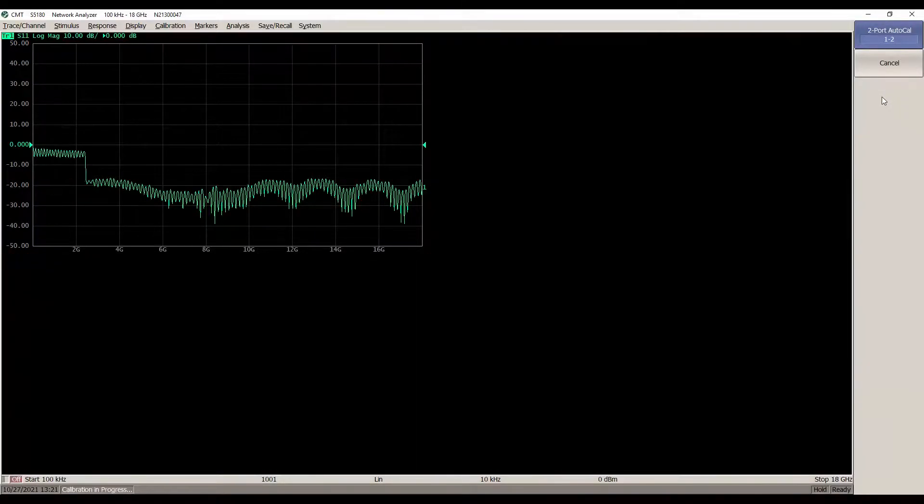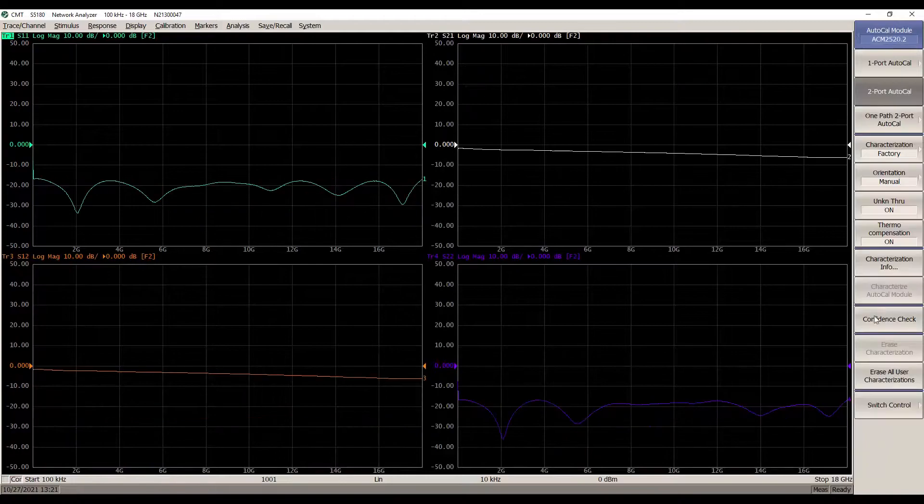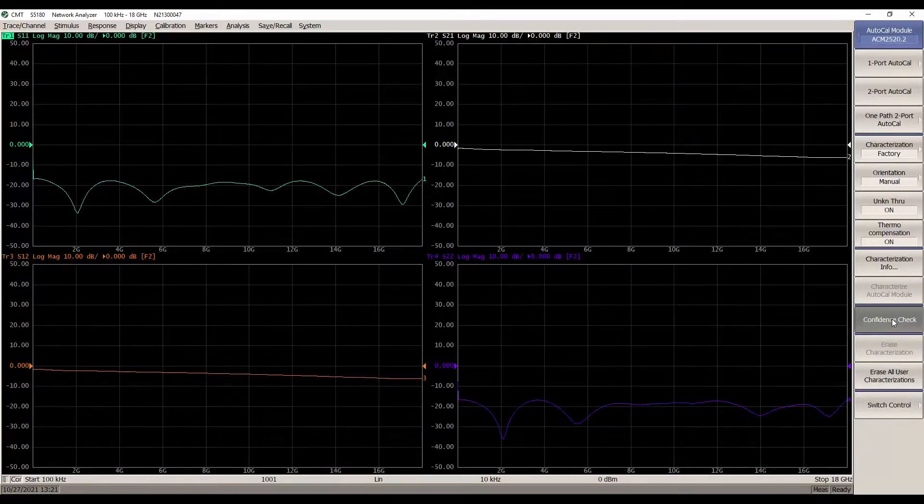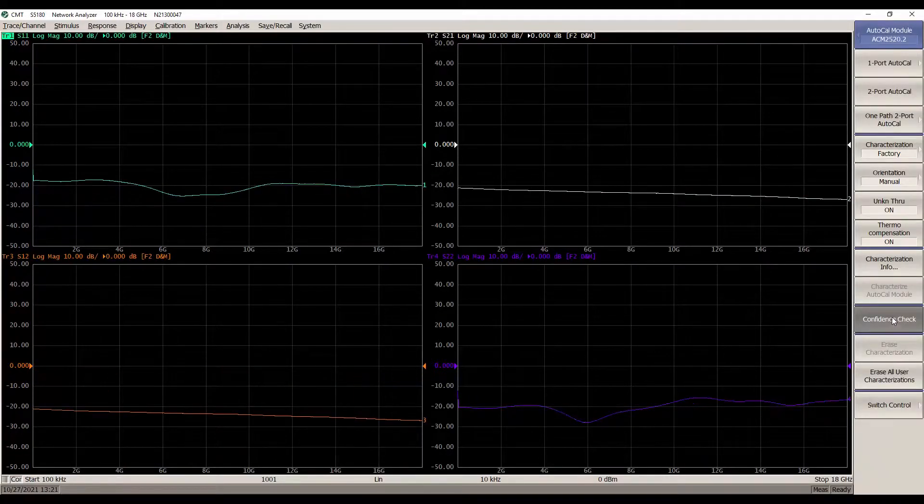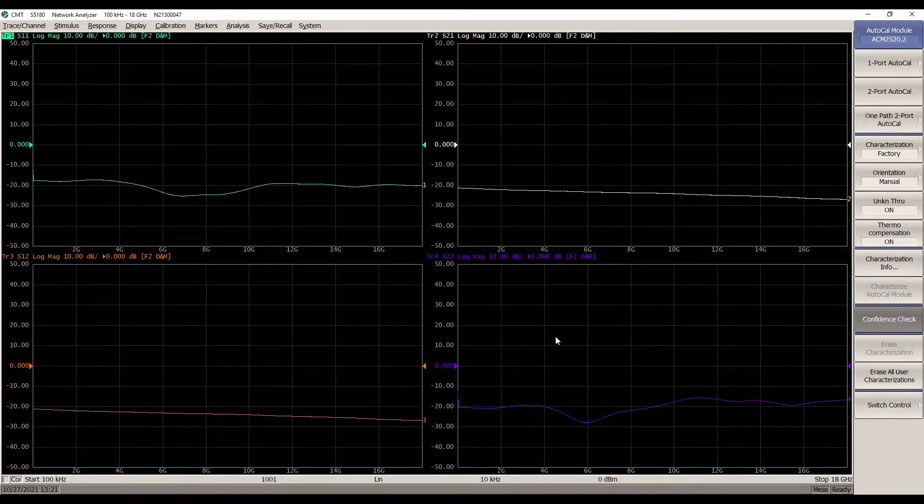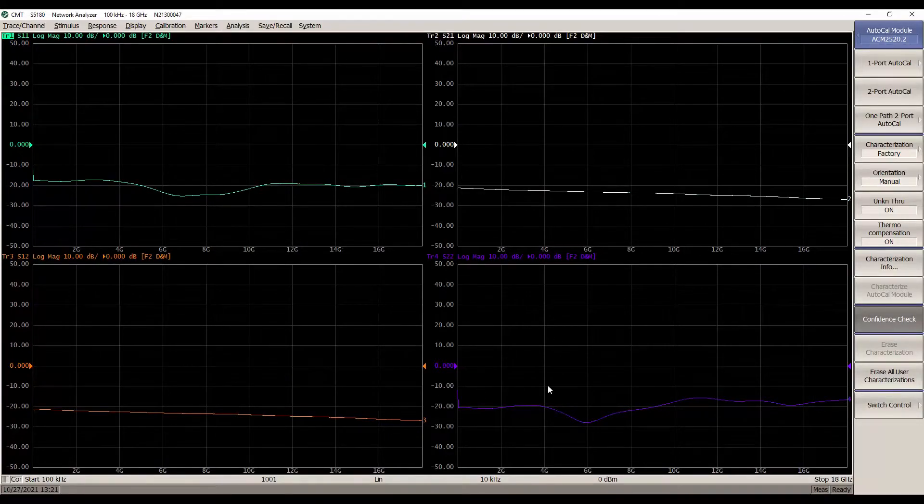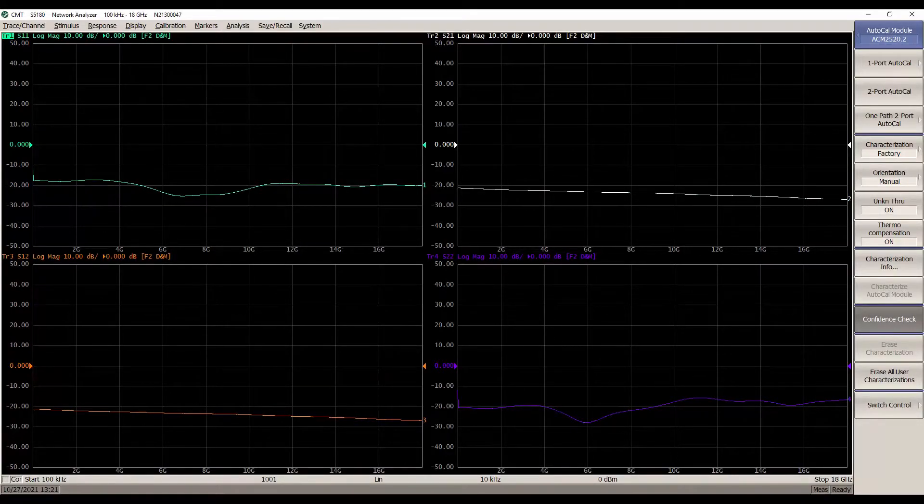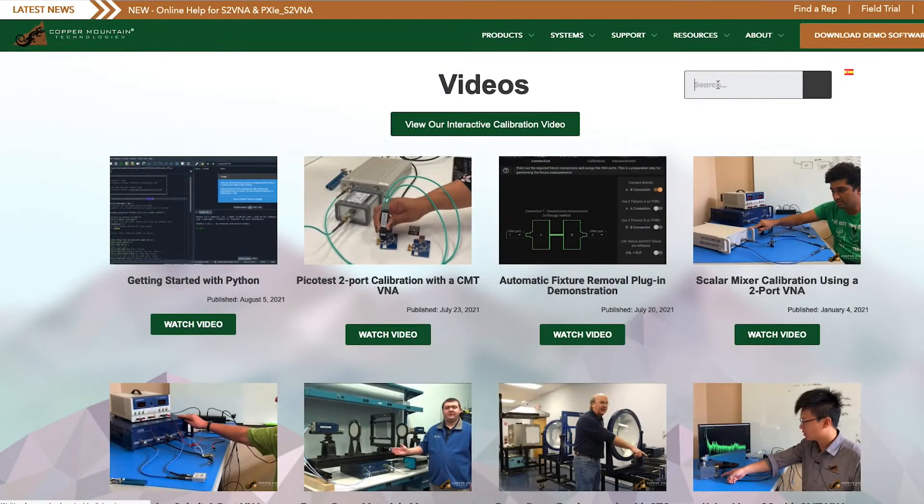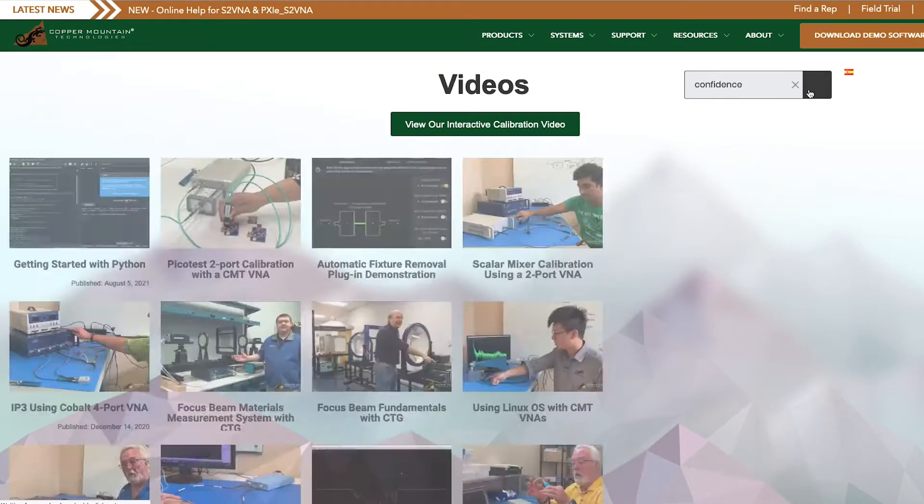You can also use the Confidence Check feature on our software to check the test setup to make sure that your calibration was successful and your cables are working properly to avoid having to retest later. We have a video showing this whole process, and you can watch to see how to use a Confidence Check after you perform your calibration.